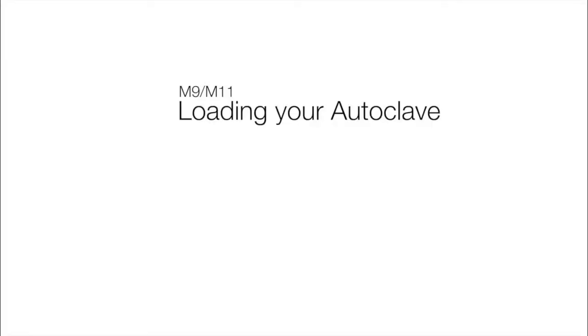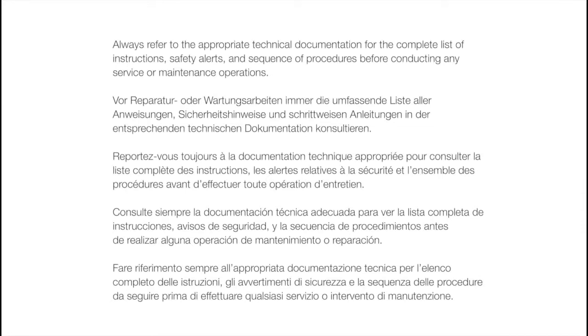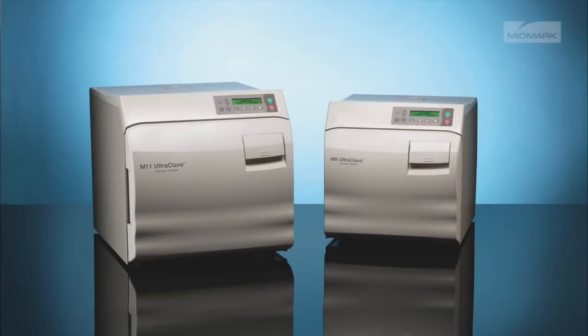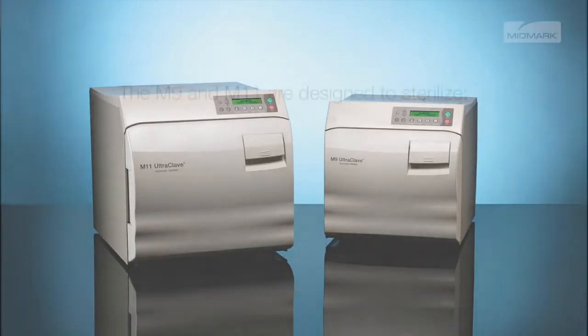This video is an overview of proper loading of your autoclave. Always refer to the appropriate technical documentation for the complete list of instructions, safety alerts, and sequence of procedures before conducting any service or maintenance operations. Before placing any instruments into the autoclave, check with the manufacturer to be sure the materials are compatible with the steam sterilization and verify acceptability of sterilization parameters.